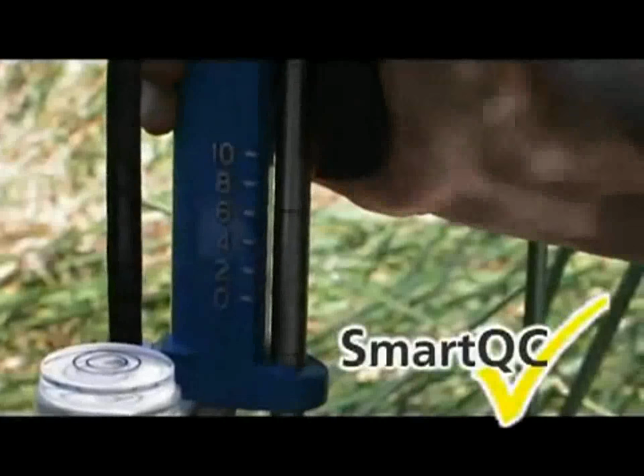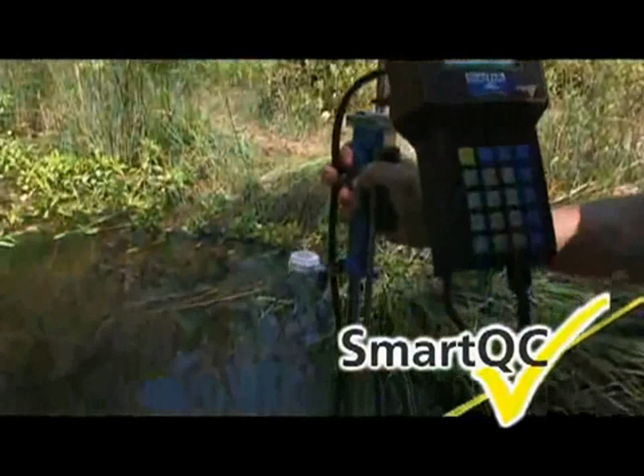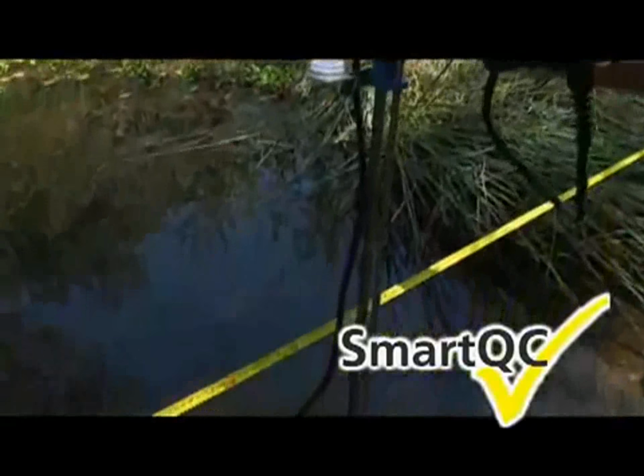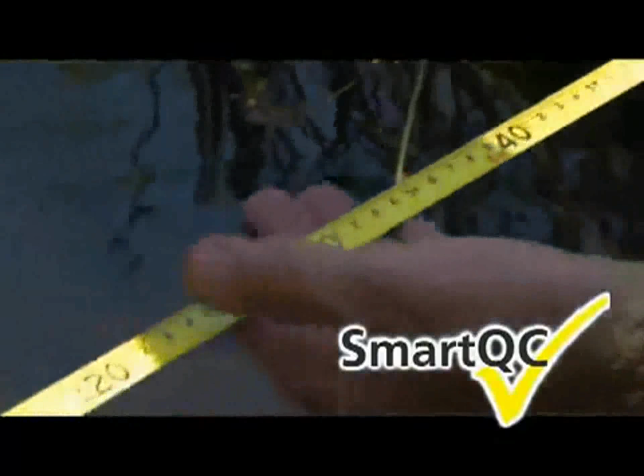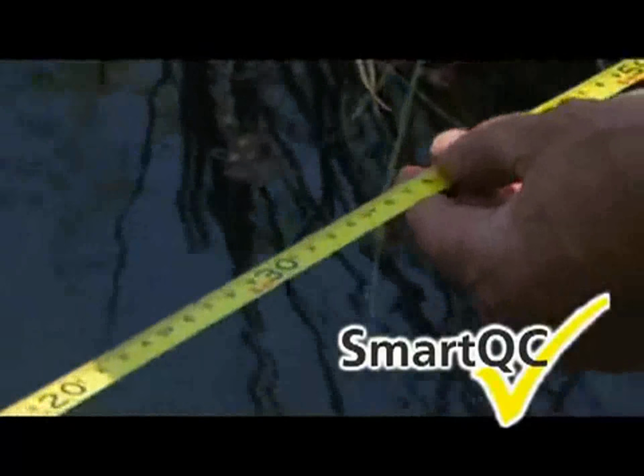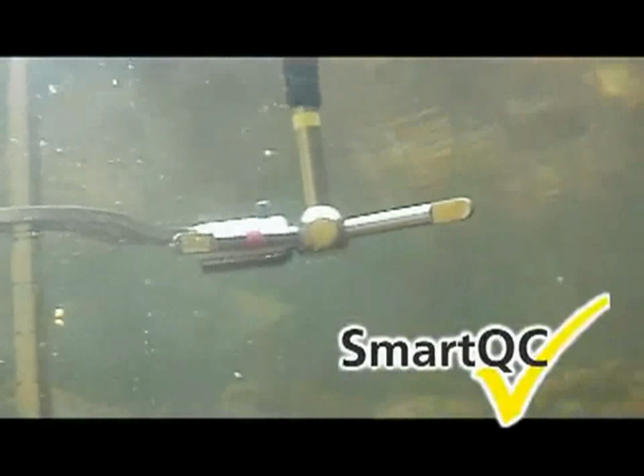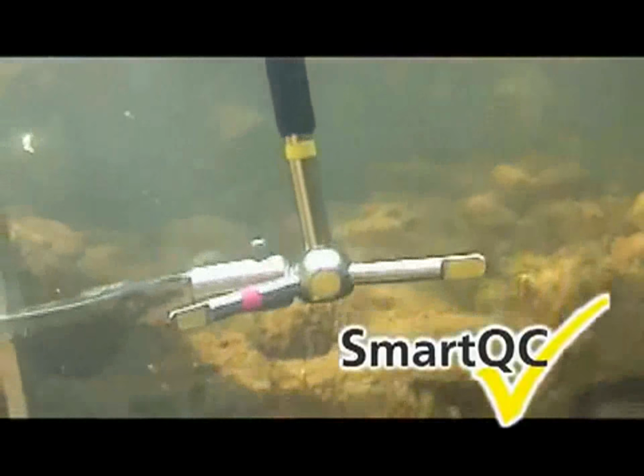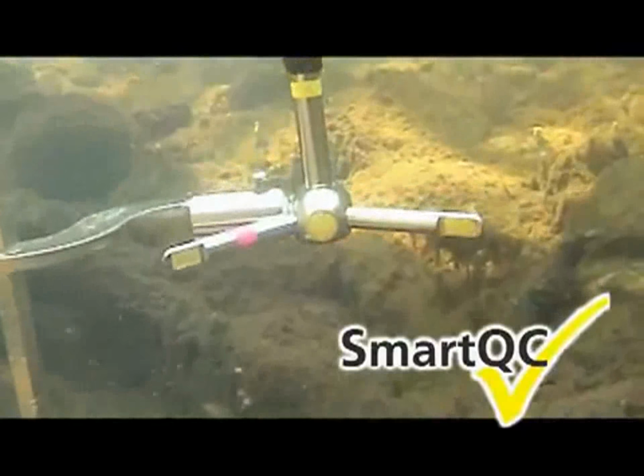A comment about Smart QC. The FlowTracker records quality control parameters with every measurement. The quality control parameters include SNR, standard error velocity, the boundary QC, spikes, the flow angle, and the percent discharge. Each QC parameter has a preset threshold from the factory that can be adjusted or disabled according to your preference.